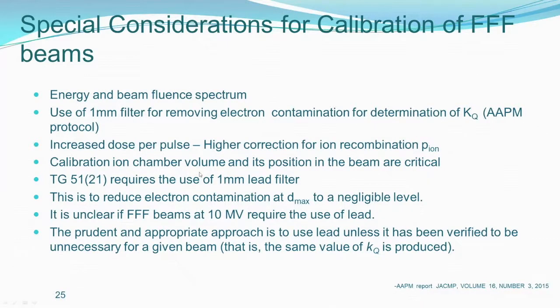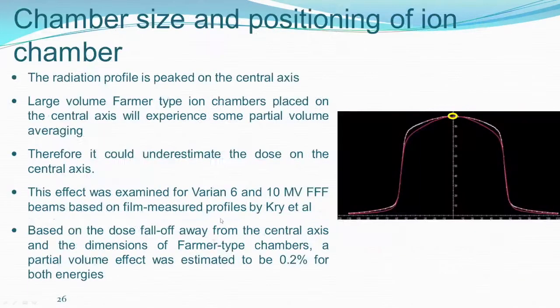Calibration of ion chamber volume and its position is very important. The volume of the ion chamber that you are going to use and how you position it in your FFF beam is important for calibration. And as I said, TG51 requires a 1 mm lead filter. This is to reduce the electron contamination at Dmax. But it's again unclear whether you need to use it or not, but it is prudent to use it. Let us look at positioning and volume of the chamber.